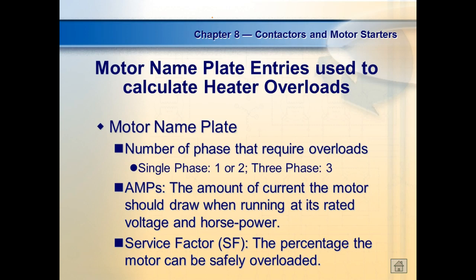Full load current, and this is the way the book teaches. They teach it as full load current. But when you look at the nameplate of the motor, you're not going to see anything called full load current. It's going to just be amps. And that is the amount of current the motor will draw when it's running at its rated voltage, at its rated speed, at its rated horsepower.